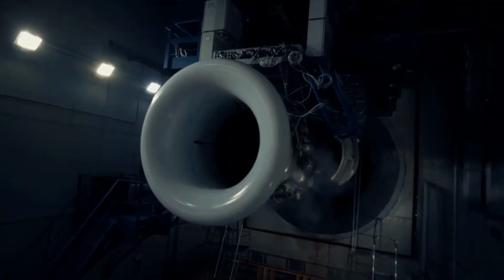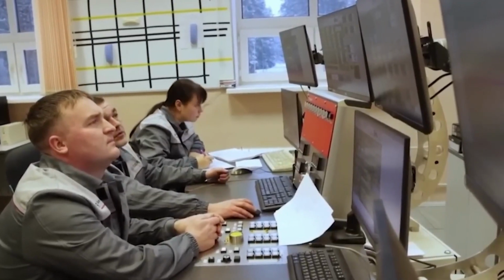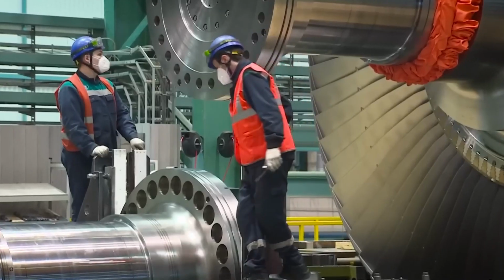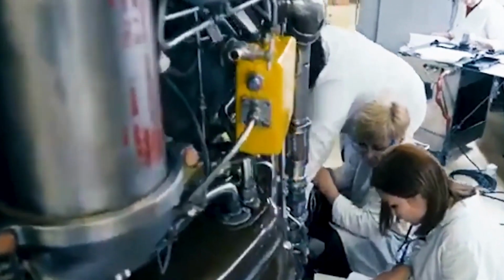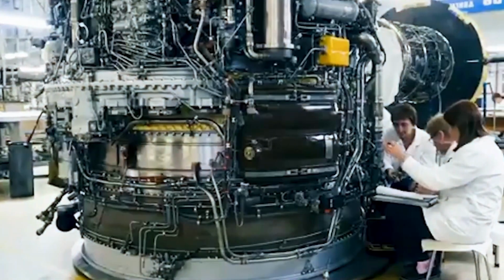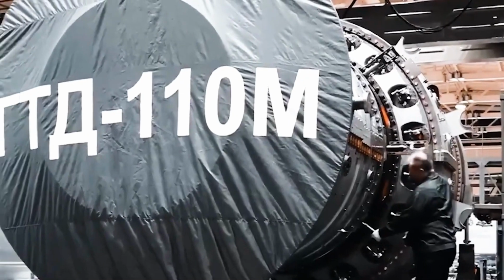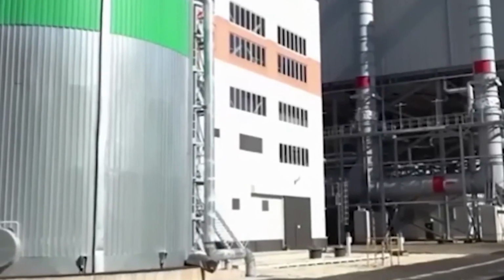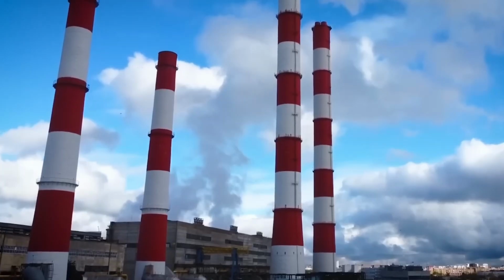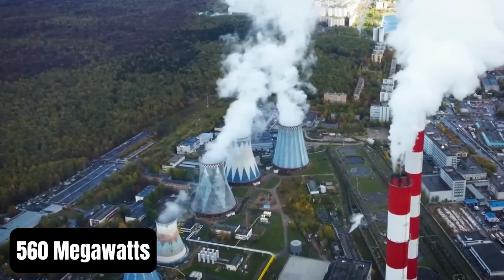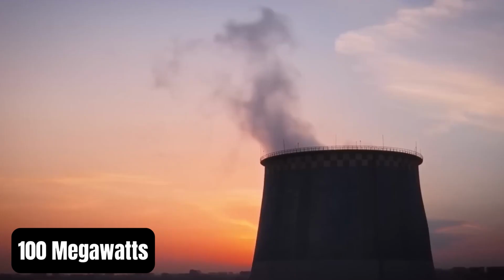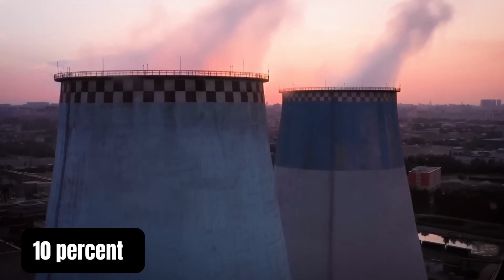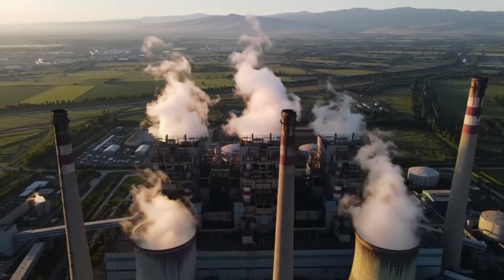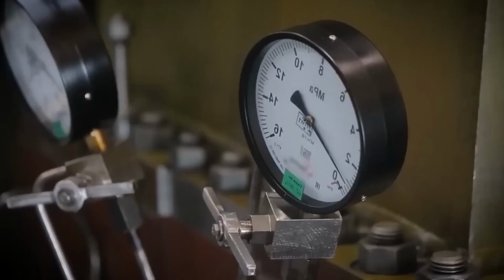Every single component, from the first engineering sketch to the last weld on the final assembly, was designed and manufactured inside Russia. The first serial unit was commissioned at the Udarnaya thermal power plant in Krasnodar territory, described by Russian energy officials as the country's most technically advanced combined-cycle thermal power plant. Before the GTD-110M was installed, that plant was producing 454 megawatts. After installation, output jumped to 560 megawatts, a gain of over 100 megawatts, enough to cover roughly 10% of the entire region's electricity demand. Those are not projections. That is measured output from a machine that is running right now.